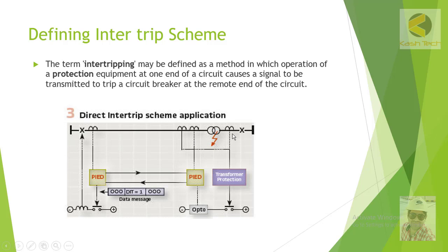There is no breaker on the transformer high voltage side, but there is a breaker on the transformer low voltage side. So if there is a fault on the line or on the transformer, in order to isolate it, since there is no local breaker, the trip signal has to be sent to the remote breaker and it should trip immediately.